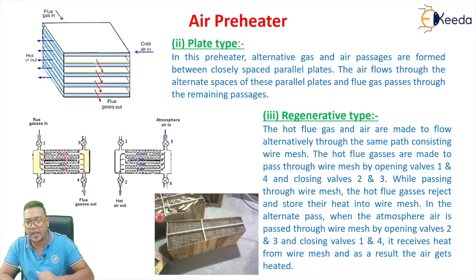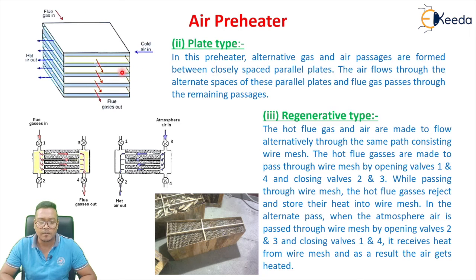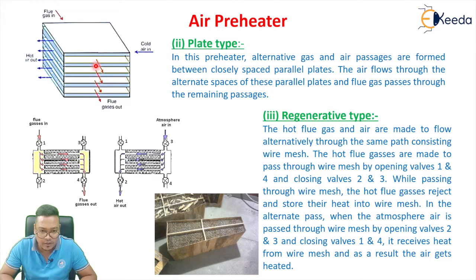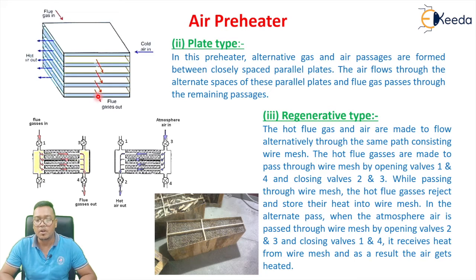In the plate type air preheater, flue gas flows alternately through certain plate passages while air flows through the adjacent passages between the plates. The flue gas and air flow through alternate passages, so that the flue gas transfers its heat to the cold air through the plates.